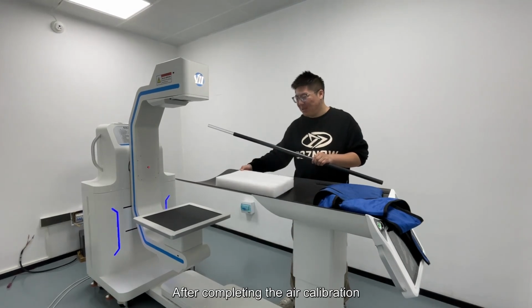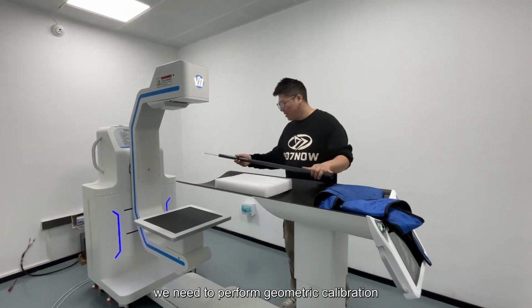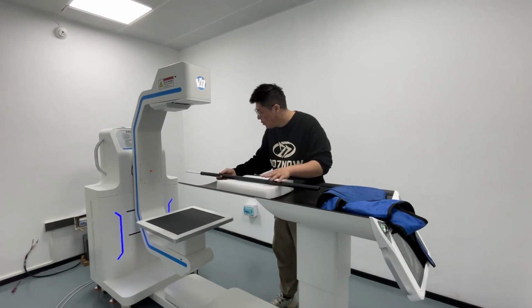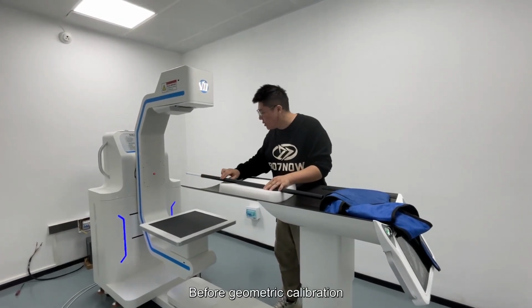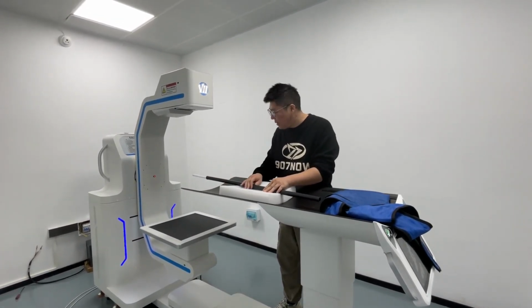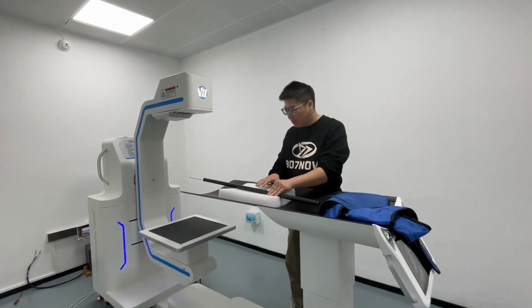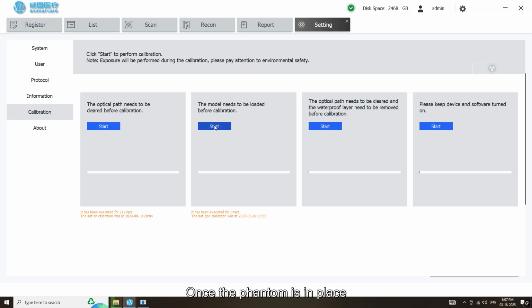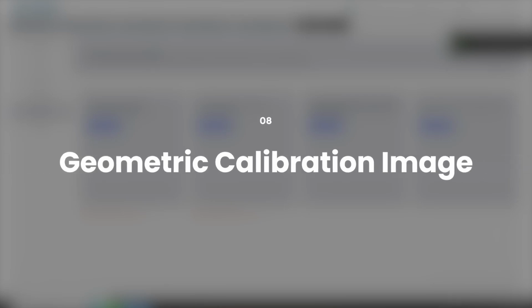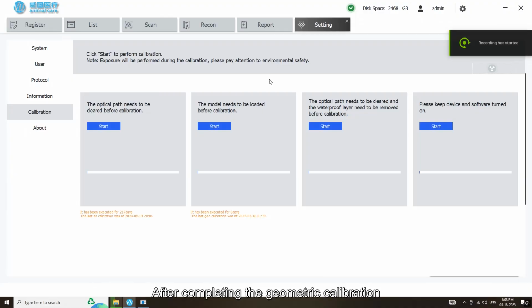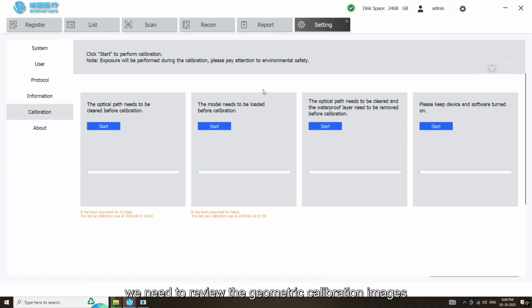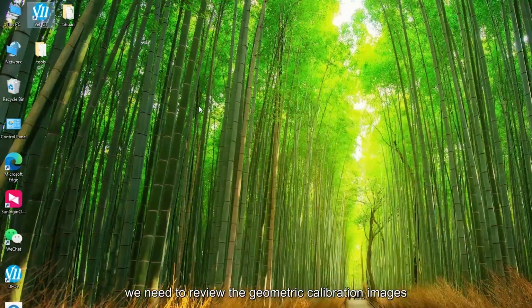7. Geometric calibration. After completing the air calibration, we need to perform geometric calibration. Before geometric calibration, place the phantom. Once the phantom is in place, click Start Calibration and wait for the process to complete. 8. Geometric calibration image. After completing the geometric calibration, we need to review the geometric calibration images.